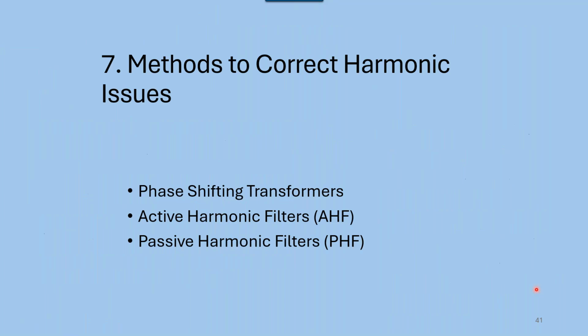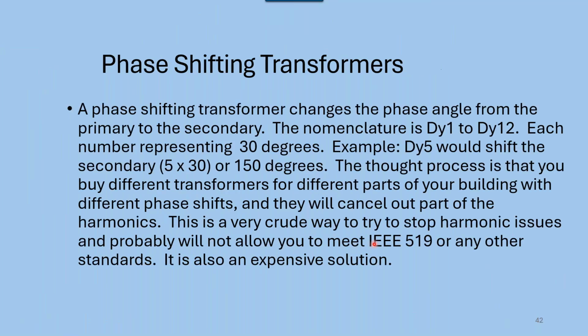All right, let's talk about methods to correct harmonic issues. The first is phase shifting transformers, and I'll have a slide on that. Then we're going to talk about active harmonic filters and then passive harmonic filters. So a phase shifting transformer, what we do is we actually can change, and if you've ever specified transformers, you'll see DY1, DY5, DY12. These are different angles that you're changing the secondary phase angle from the primary, okay?